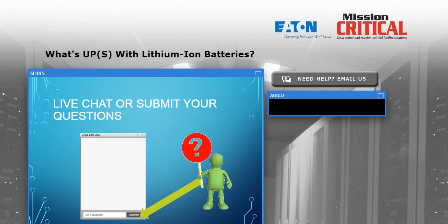What kind of thermal overload is in this battery, and what conditions does it show before it fails? So what will happen is the battery, of course, begins to get too warm, due to possible overcharging, or maybe the ambient temperature got dramatically hotter for some reason while the battery was charging. So when we start to see a battery or a battery cell that is getting too warm, the management system is going to take action to reduce or even turn off all charge current to that particular battery. So it can do that on an individual basis, which is good, and allows the rest of the battery to continue to function. However, if we take those steps to reduce or disconnect the battery charge and that battery continues to get warm, remember we're watching the temperature of every single battery as well. So if it continues to get warm in that case, we are simply going to bypass that battery and effectively disconnect it from the string. We're going to jumper around it, so to speak.